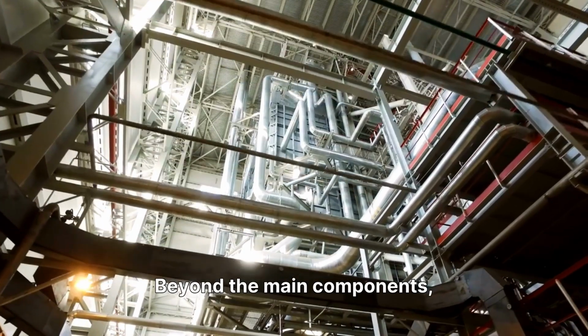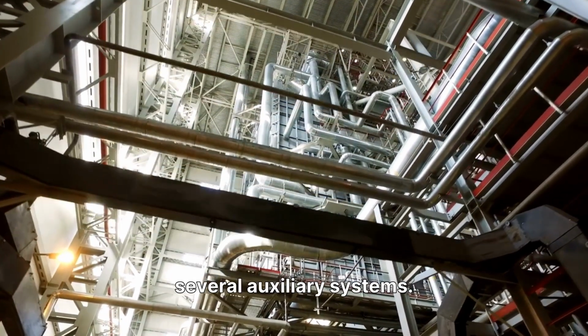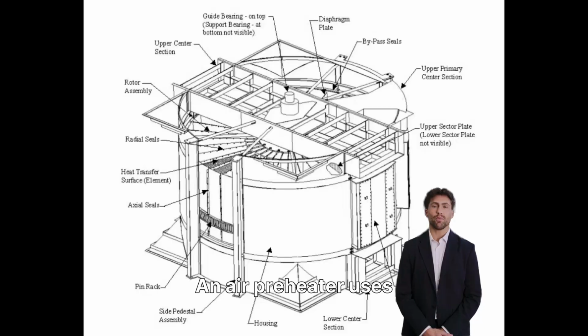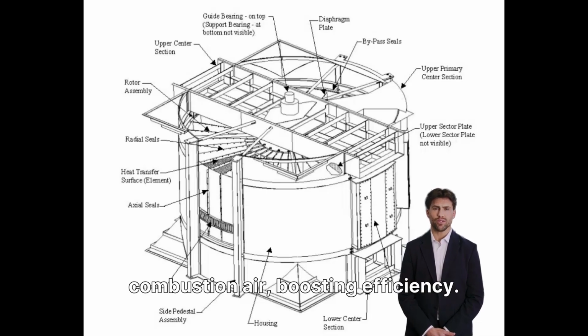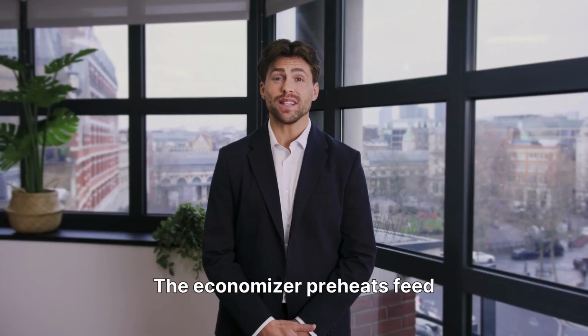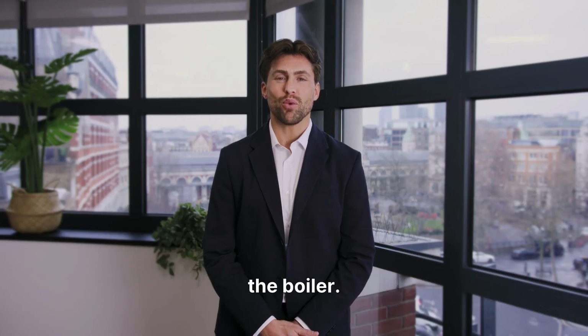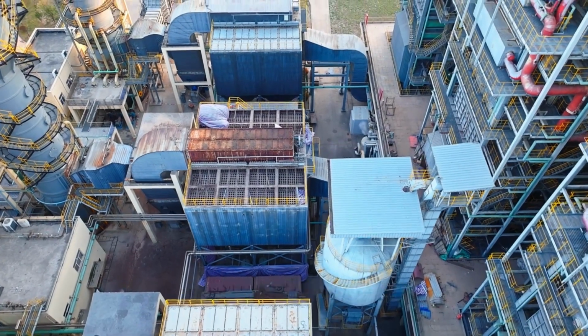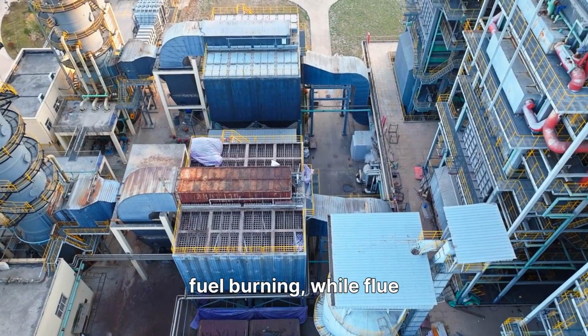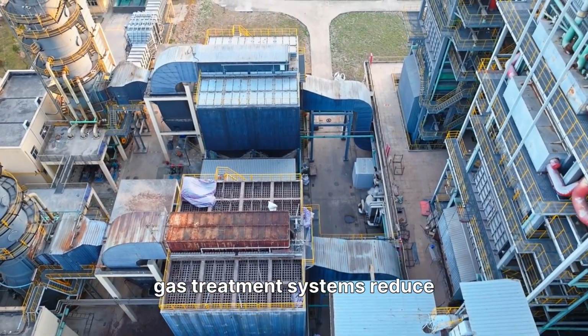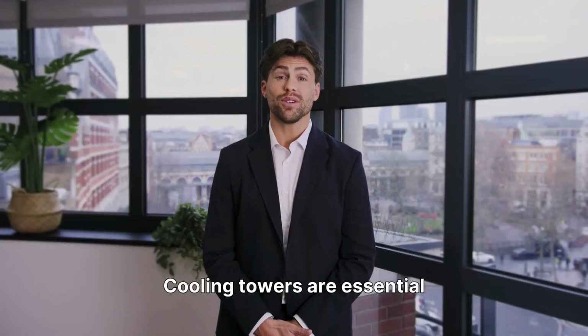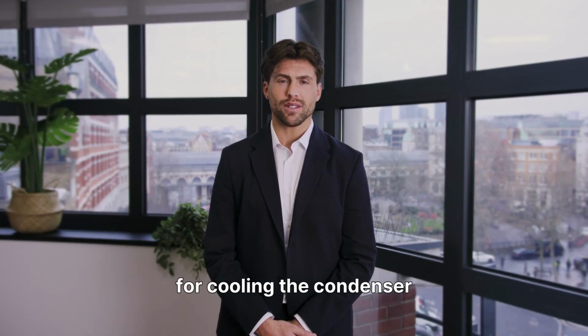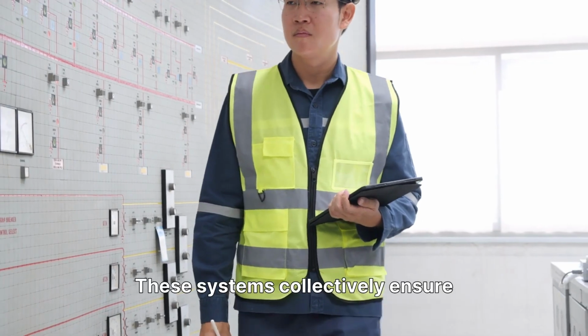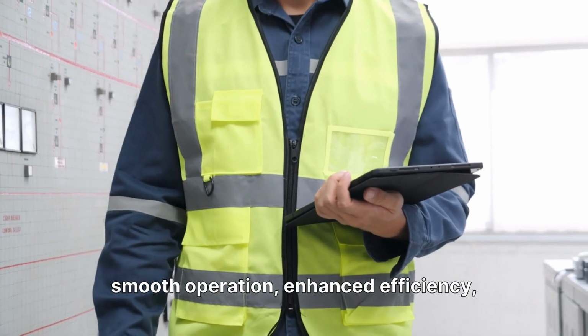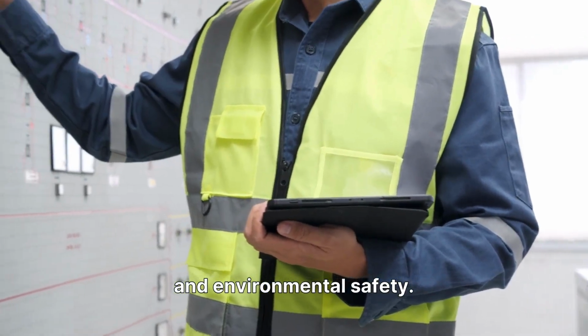Beyond the main components, a power plant incorporates several auxiliary systems. An air preheater uses flue gas to preheat combustion air, boosting efficiency. The economizer preheats feed water before it enters the boiler. An ash handling system efficiently removes ash after fuel burning, while flue gas treatment systems reduce pollution. Cooling towers are essential for cooling the condenser water. These systems collectively ensure smooth operation, enhanced efficiency, and environmental safety.